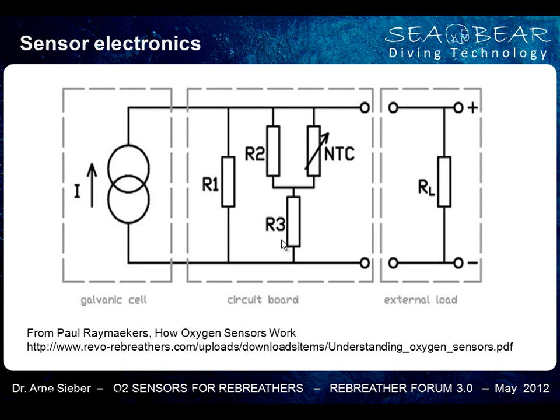Today, Bill Stone showed a picture of two sensors that were deviating from each other because of different temperatures. One important thing is that these sensors and resistors all have certain tolerances. So even if they're assembled correctly, you might not achieve perfect temperature compensation, especially if you calibrate the sensors at a completely different temperature than you use them in the end.